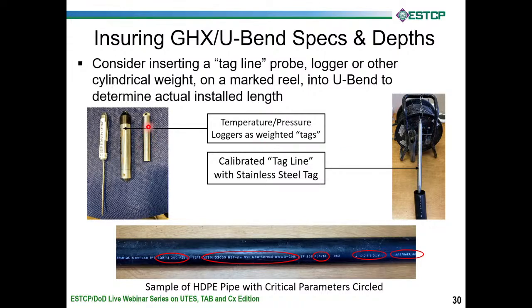When we do thermal conductivity testing, we actually drop temperature loggers down into the ground and measure the temperature underground at various depths, as we're trying to determine what the deep earth temperature is, because it varies with depth. But anyway, you drop one of these down into one end of the U-bend after you've completed the initial pressure testing and cut those Schrader valves off I showed you earlier. And we like to verify the length of at least a representative number of U-bends to make sure we're not getting short looped, because regrettably, occasionally you will have contractors that short loop you.